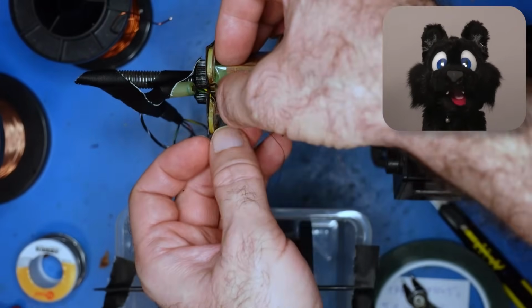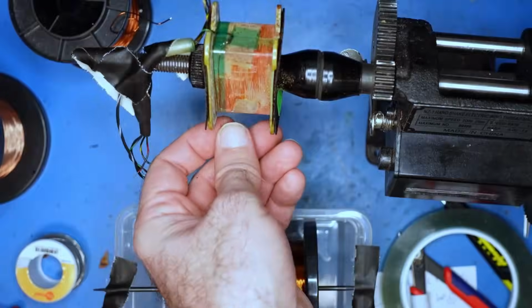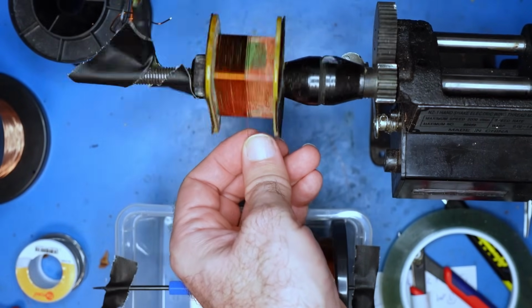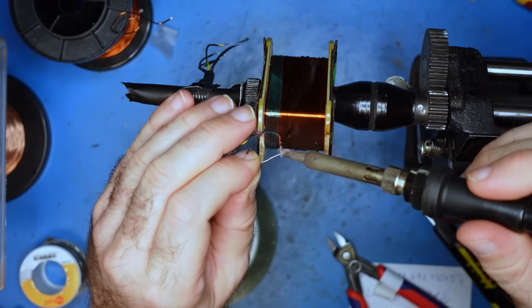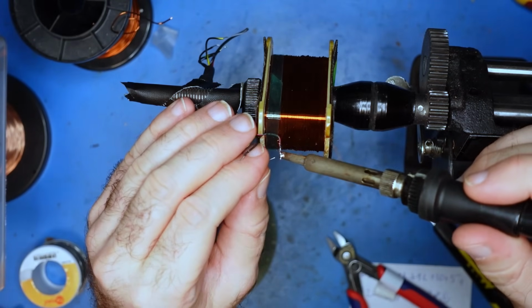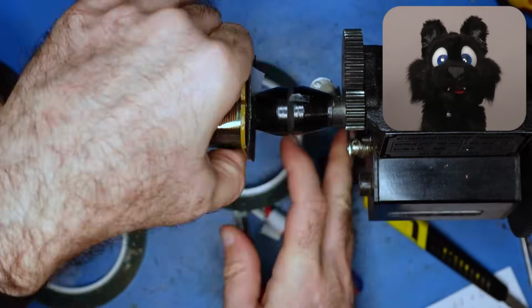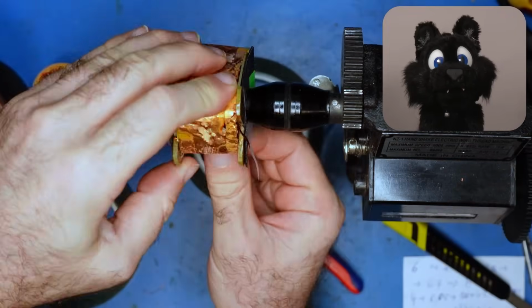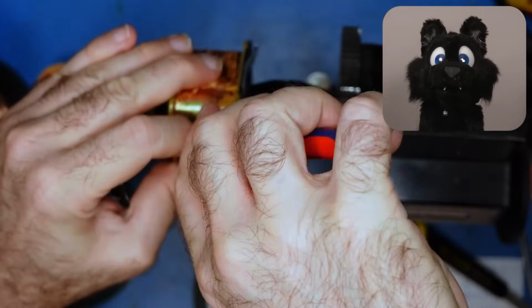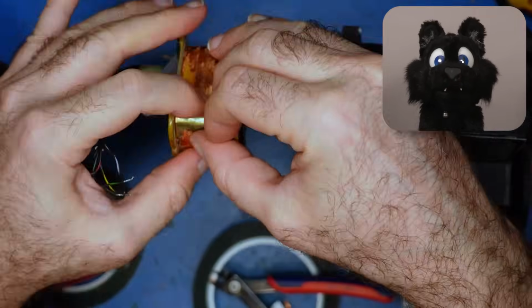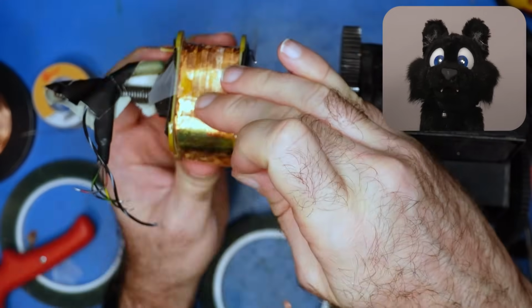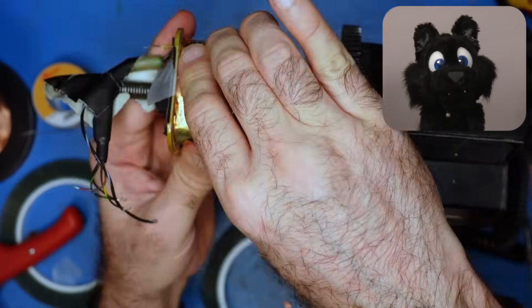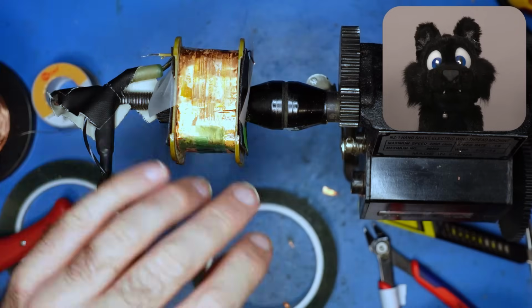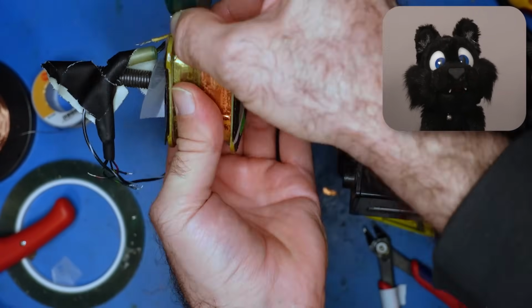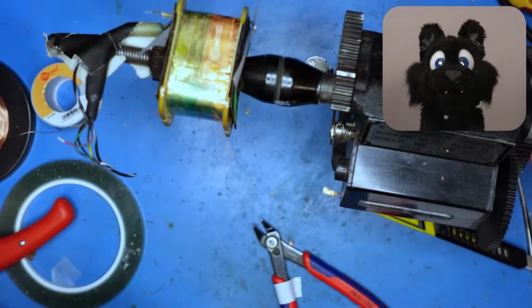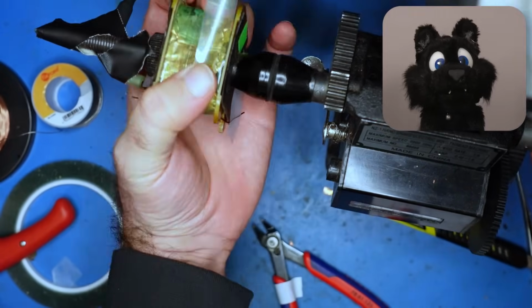Winding the new primaries first. Followed by a sandwich of insulation and 2 shielding layers. A comment on an older video suggested that these might cause the transformer to heat up because they end up as one winding and would make heat. I think they originally were a single loop, but I can see the argument, so I'm wrapping them with a bit of insulation between the ends so they don't make contact.